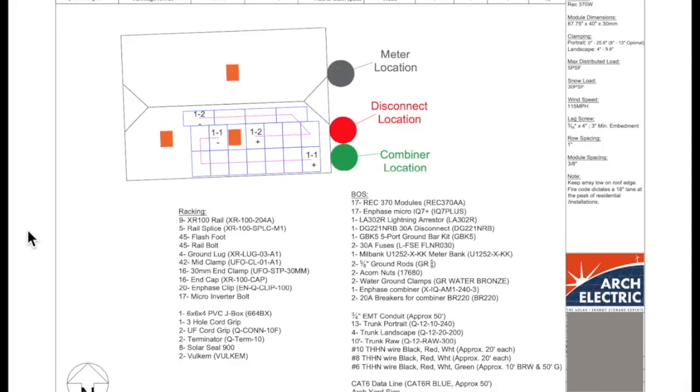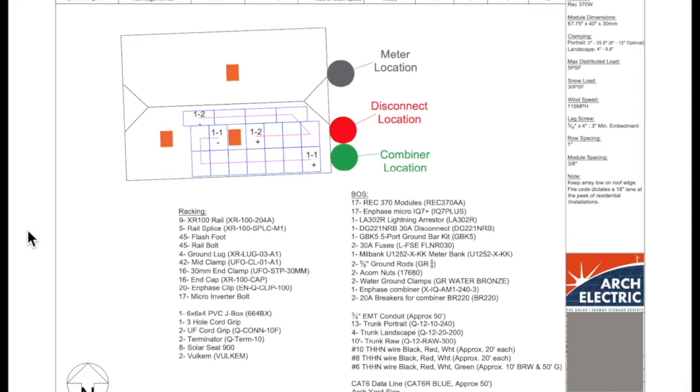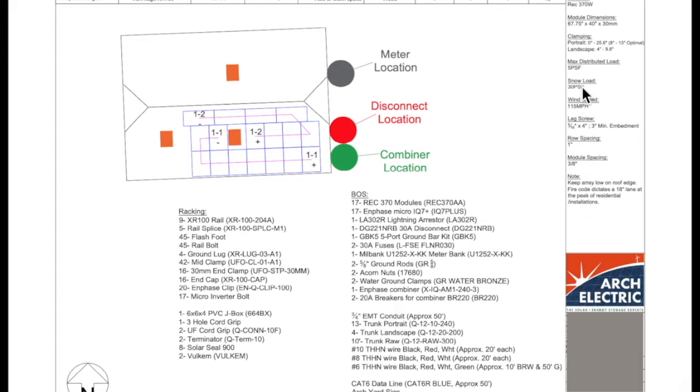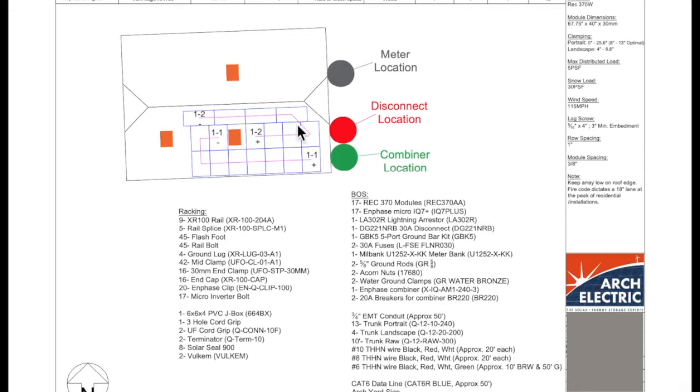And they get into some information. This is a bill of materials, basically explaining exactly how things are going to get wired together, what fasteners they're using, the make and model of all sorts of different parts and pieces, so that if something doesn't show up on site or isn't installed, you can question it and say, isn't this missing? They also have some information here about the anchoring and the wind load. So there's actual civil engineering numbers that go into this and information about the property and how they're being laid out. So the type of spacing, the way that the actual array is being wired up, there's actually two different strings. So there's one breaker for each one in the combiner. Snow load, wind speed, and so on and so forth.